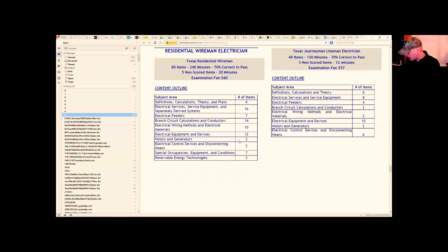I don't go around calling PVC rigid, non-metallic raceway, so that's why I'm telling you to put PVC on top of column 3. So Schedule 80 or Schedule 40, either one would fall under column 3. UF cable or USE cable, any kind of underground service entrance cable, would fall under column 1.